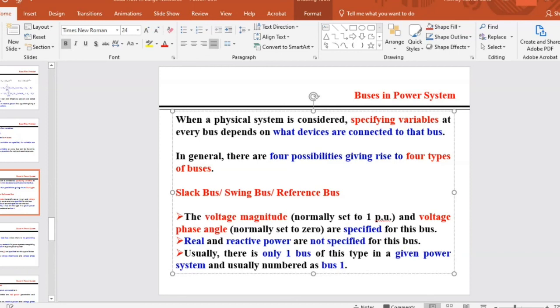So in most applications, bus number one is the slack bus, because that's where the largest generation capacity is connected. But in some cases, bus 9 or bus 3 might be the slack bus instead. We'll know that the voltage magnitude and phase angle are known, given, specified, or set by us. The phase angle is normally chosen as 0 degrees, and the voltage magnitude is chosen as 1 per unit at the start of the power flow calculation. It will change later depending on how much load is connected to which bus.